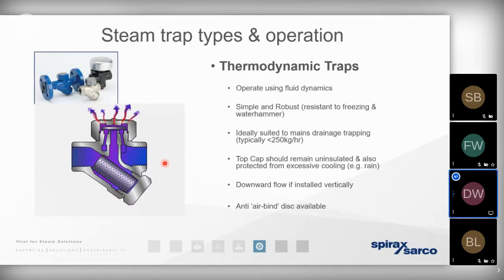On the downside, we do need to ensure that we're venting away any air that is present in the steam distribution network upstream of this trap. And that's because it simply cannot tell the difference between steam and air. So any air that is present will cause what we refer to as air locking. The other thing to bear in mind is we'd never lag this type of trap. And that's because we need to allow for that flash steam to condense very, very quickly. If we lagged it, there'd be a delay in the rate of that flash steam condensing. In other words, we'd be derating the capacity of this type of trap by lagging it.